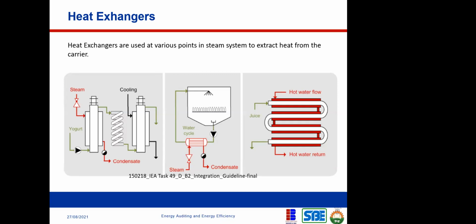So let us look at heat exchangers. Heat exchangers are used at various points in the steam system to extract heat from the carrier. Remember that the boiler generates the heat. The boiler heats the water and converts that water into steam. Then there's a steam distribution system that transports that steam from the boiler to the point where it is needed for an industrial purpose. At that point, what you have is a heat exchanger. The heat exchanger extracts the heat from that steam and transfers that heat into the industrial process that you want. Once that happens, part of the steam condenses and returns back to water. And then you have the steam trap to remove that water.